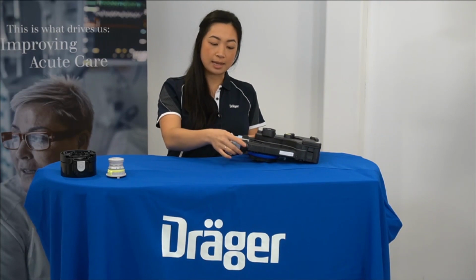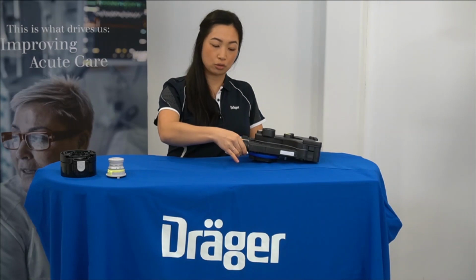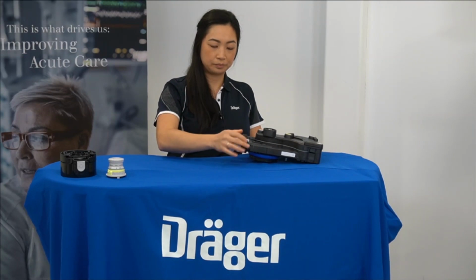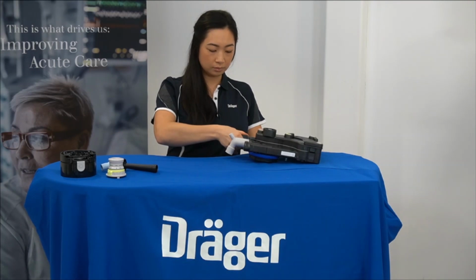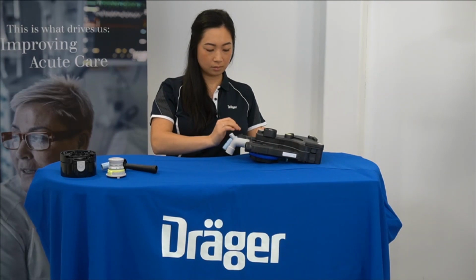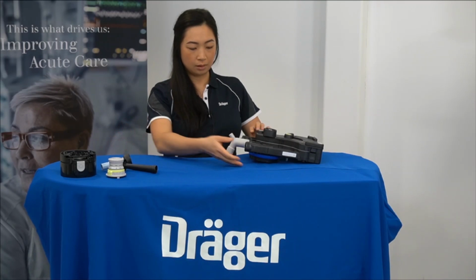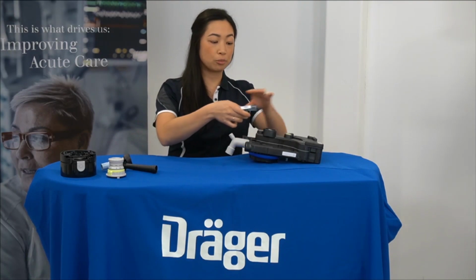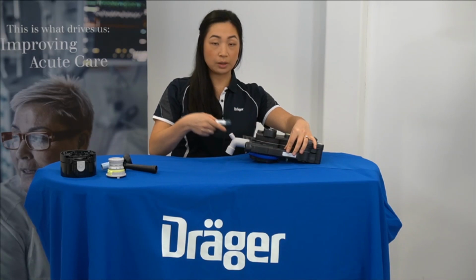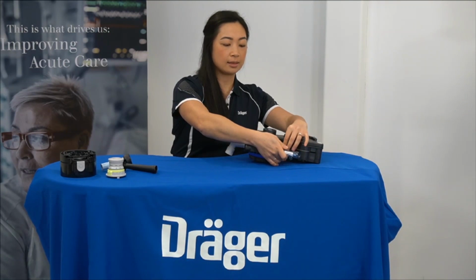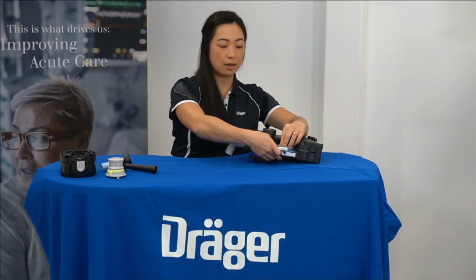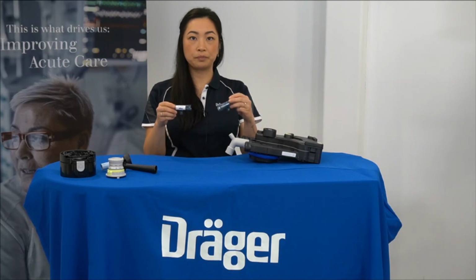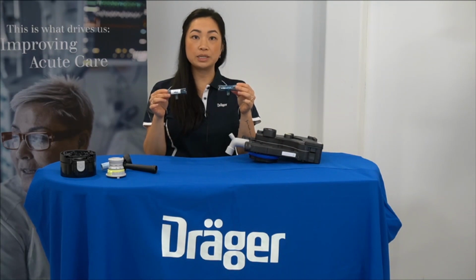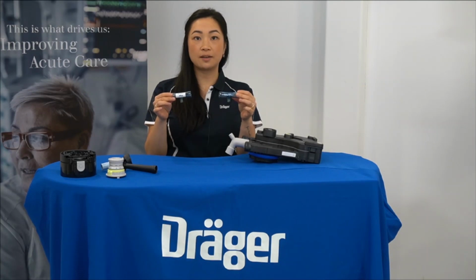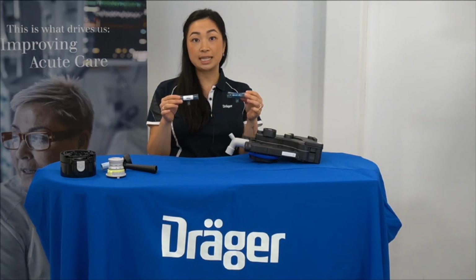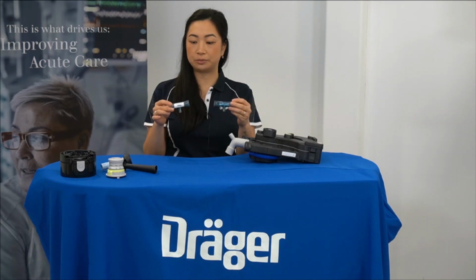Following that, the inspiratory and expiratory ports can be unscrewed from the breathing system. You will then be able to remove the flow sensors, first one from the end of the port and the expiratory flow sensor from the middle of the port. These can then either be disposed of or reprocessed via immersion. Please refer to the instructions for use for further information.